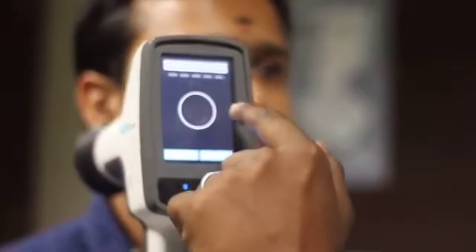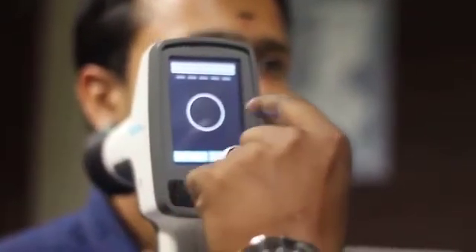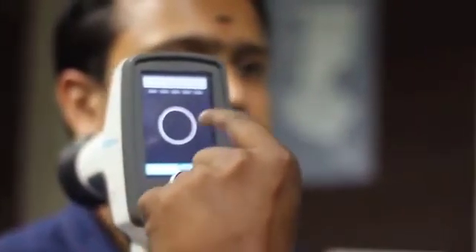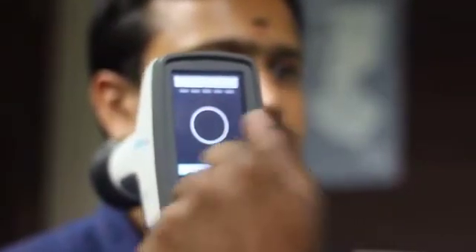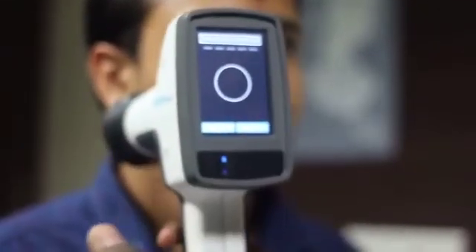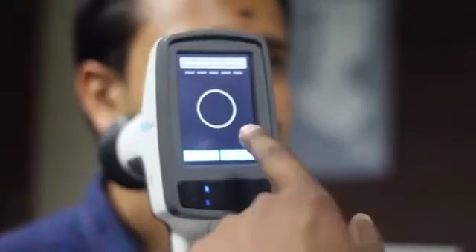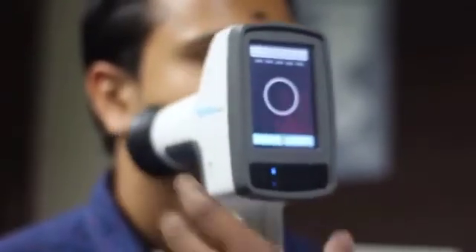The circular grid helps us align with the patient's pupil. Now I will show a demo of how to align the circular grid with the patient's pupil.